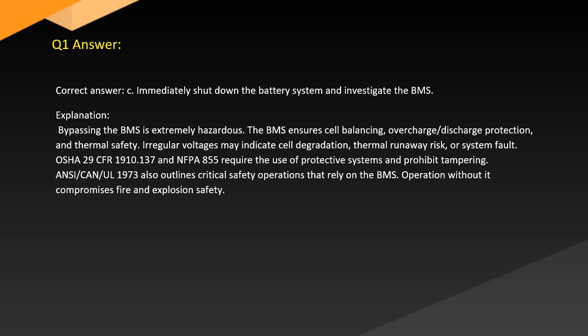OSHA 29 CFR 1910.137 and NFPA 855 require the use of protective systems and prohibit tampering. ANSI/CAN/UL 1973 also outlines critical safety operations that rely on the BMS. Operation without it compromises fire and explosion safety.